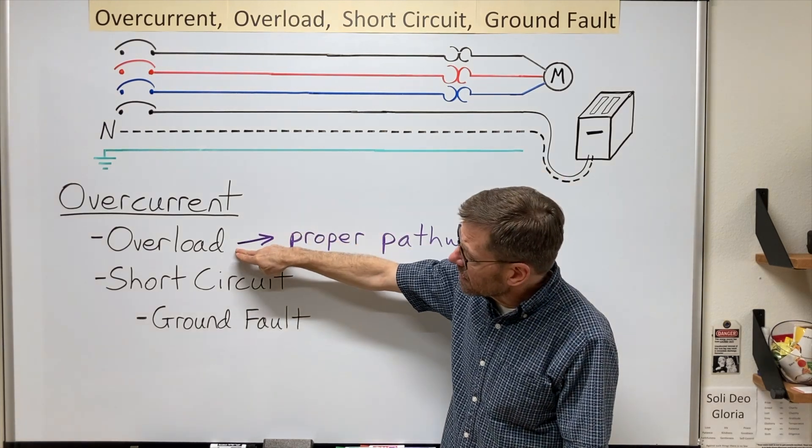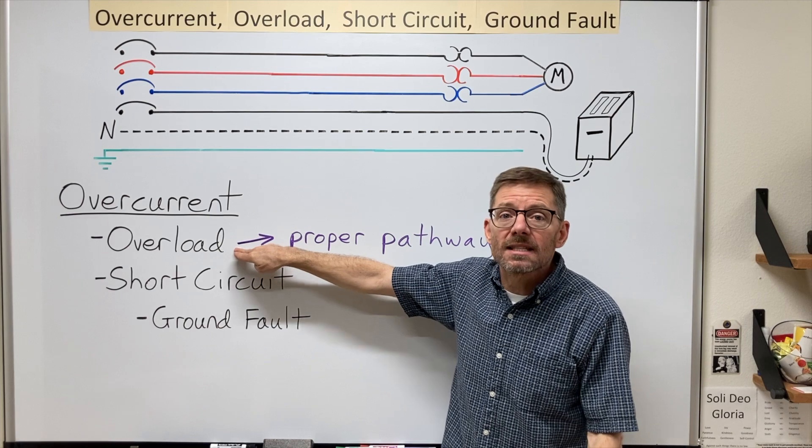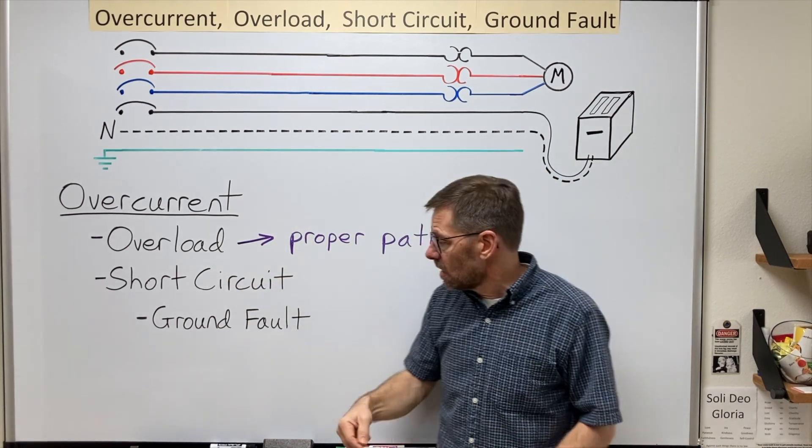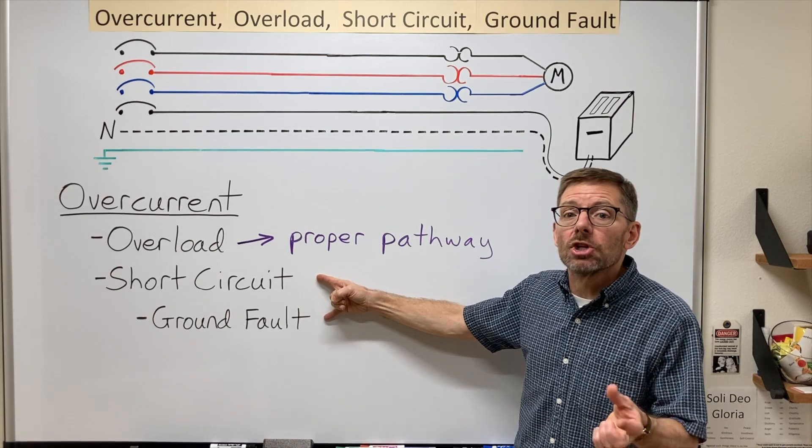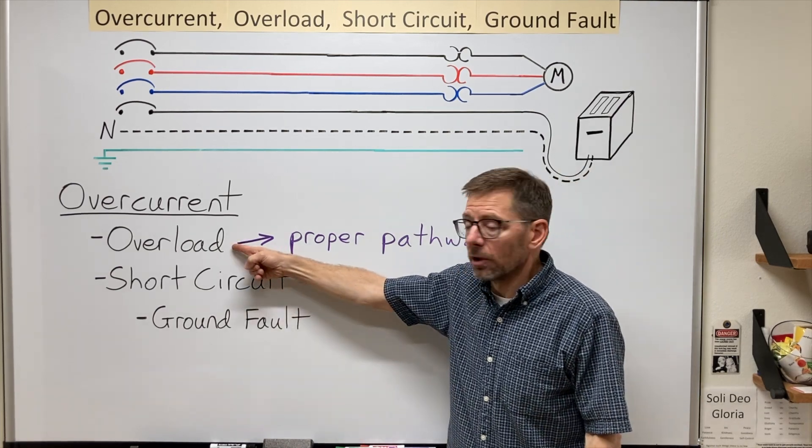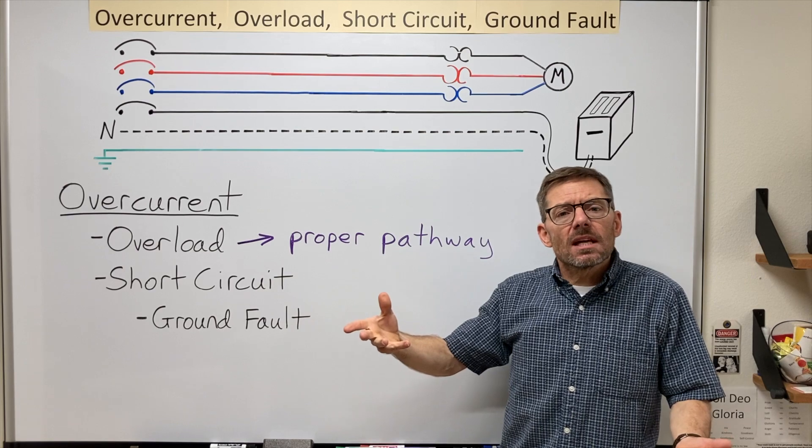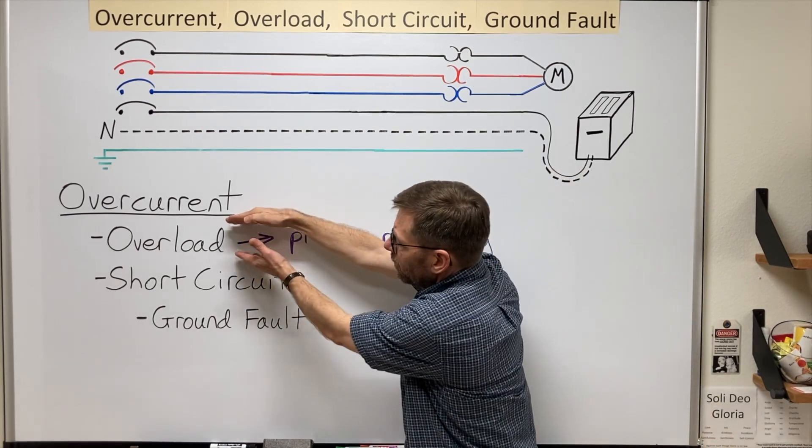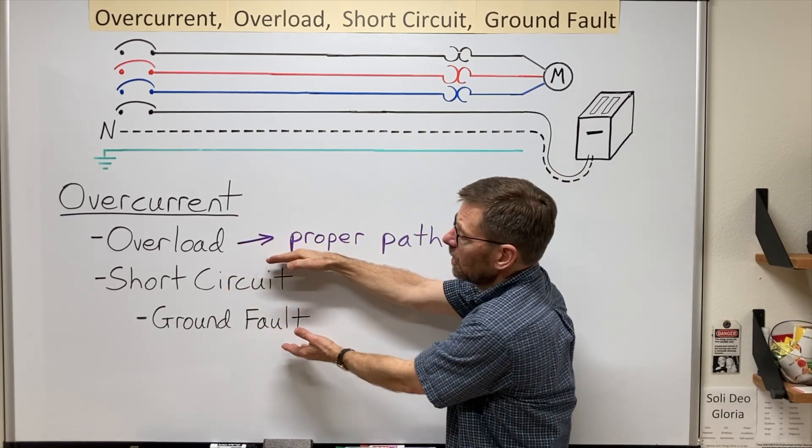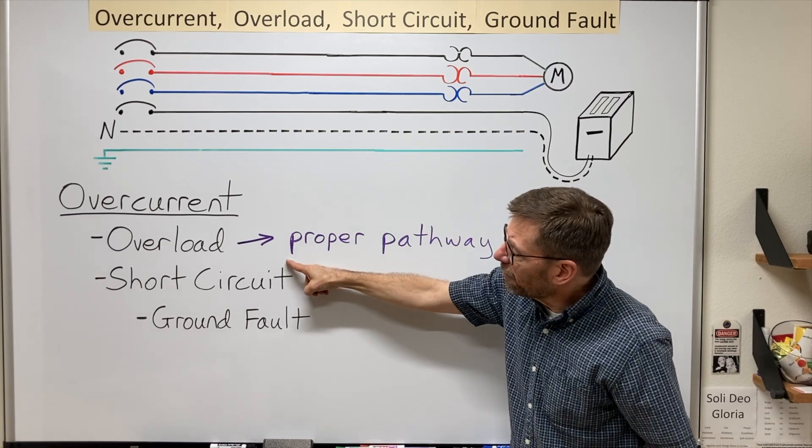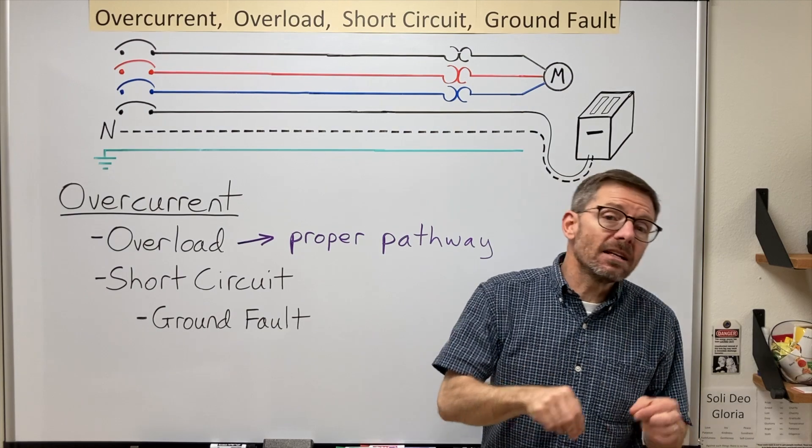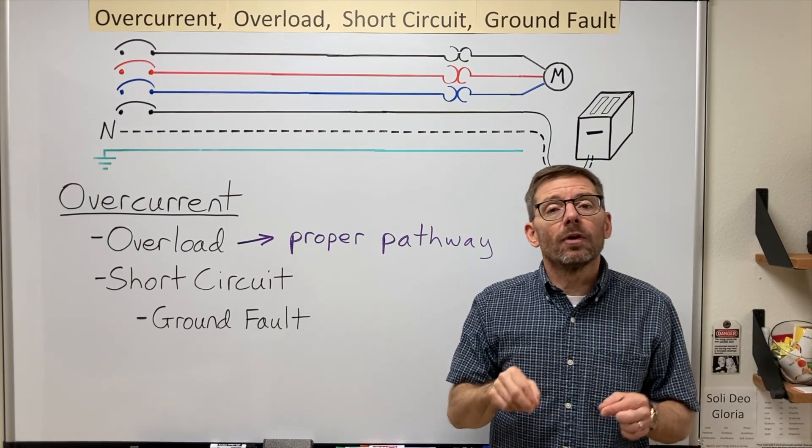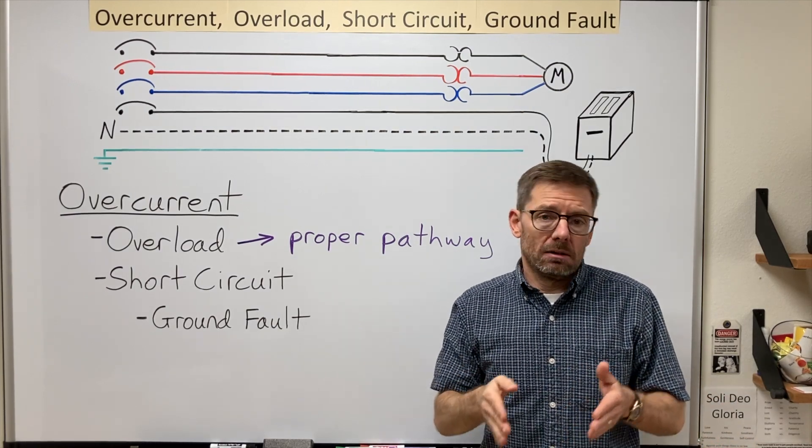But the final sentence under overload says that a fault, such as a short circuit or a ground fault, is not an overload. So what's the main distinction between overload and these faults? Well, I'm going to say that these fault currents are not flowing in the intended pathway. They are flowing in a wrong pathway.